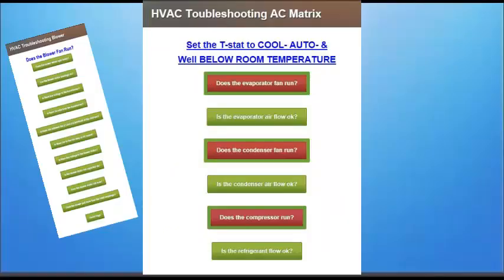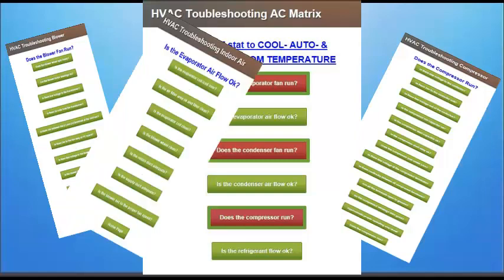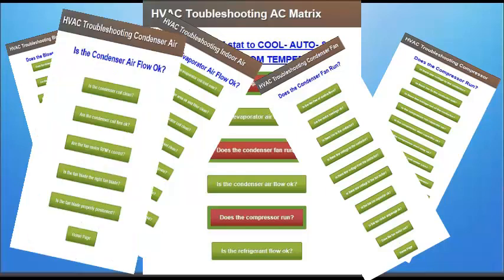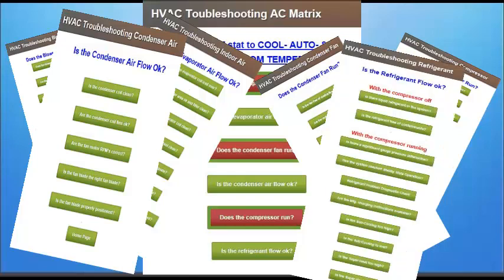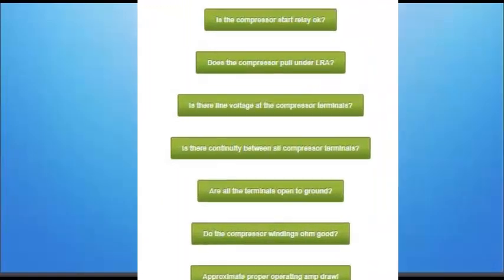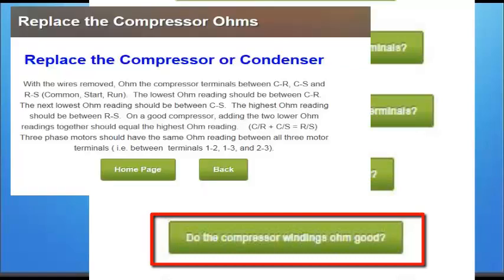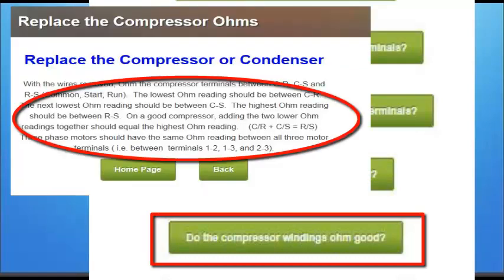Any negative answers prompt another set of questions in the technician's mind. These questions are also mentally prioritized and sequenced in the proper order for the most efficient and effective troubleshooting. Answering any of these secondary questions will involve a subtle shift from the process of troubleshooting to the knowledge necessary to use troubleshooting procedures. For example, in order to determine if the compressor ohms good, the technician must already know at least one ohm test procedure. In this case, the matrix does provide one common ohm testing procedure often used to evaluate compressor windings.